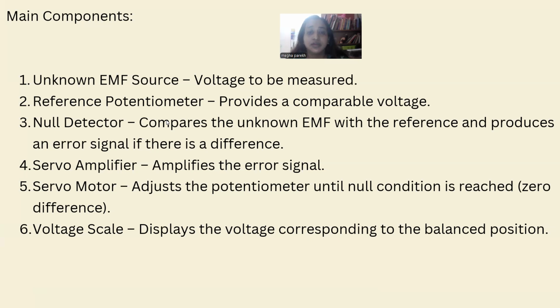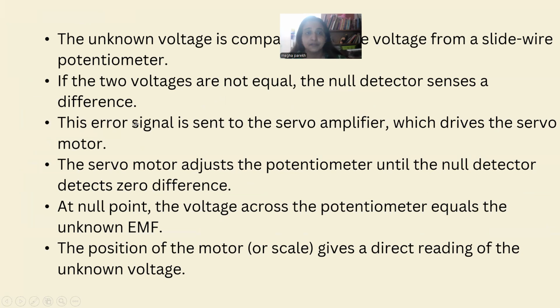The unknown EMF source is the voltage to be measured. The reference potentiometer provides the comparable voltage. The null detector compares the unknown EMF with the reference and produces an error signal if there is a difference. The servo amplifier amplifies the error signal, and the servo motor adjusts the potentiometer until the null condition is reached. And lastly, the voltage scale displays the voltage corresponding to the balance position.